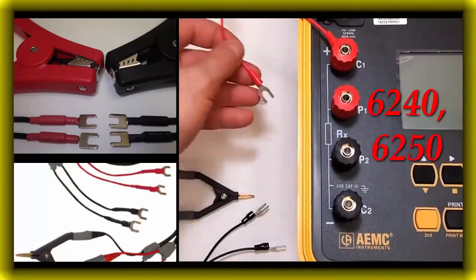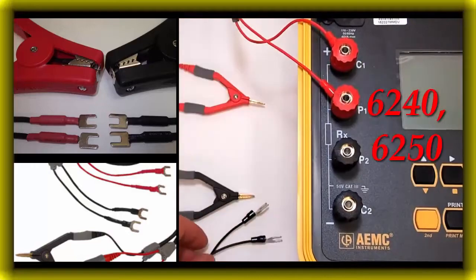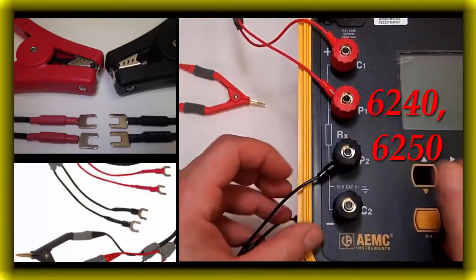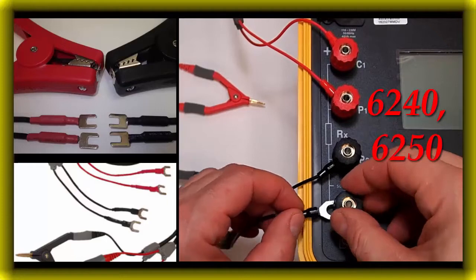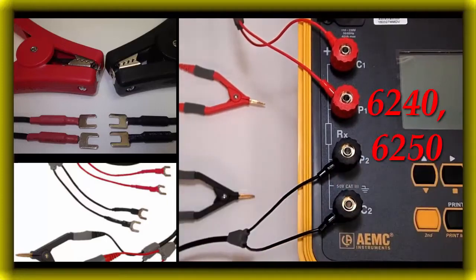For probes 1 and 2, red lead to red C and red P on the instrument, black lead to black C and black P on the instrument. You still need to be mindful of their orientation in that the black lead connected to C2 and the red lead connected to C1 need to be the same side of the jaw for the most accurate results.